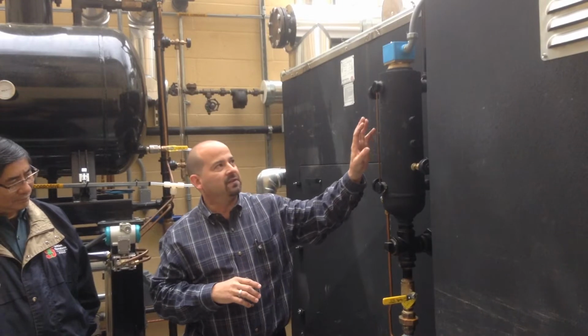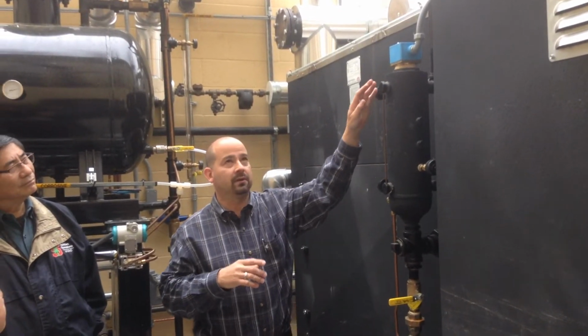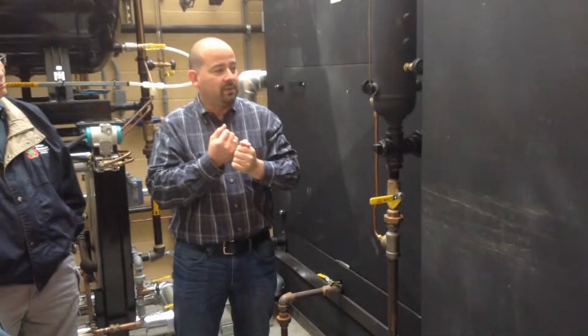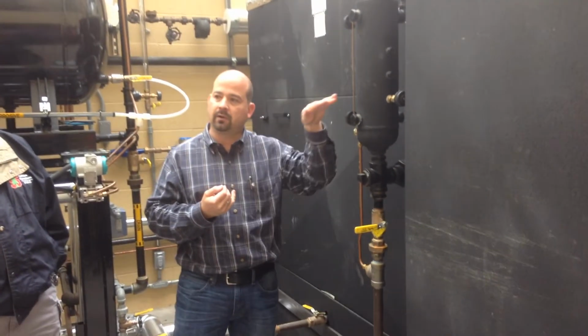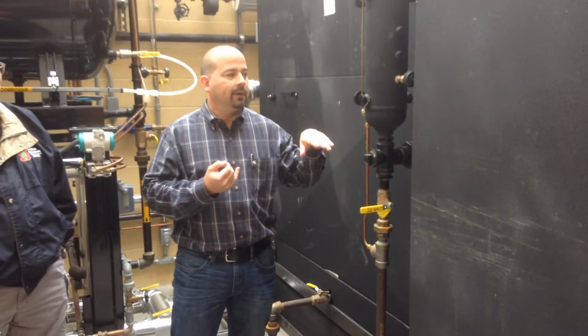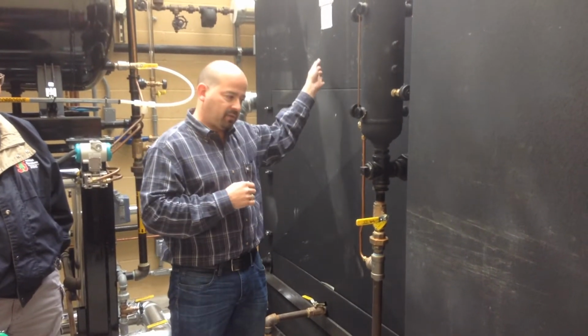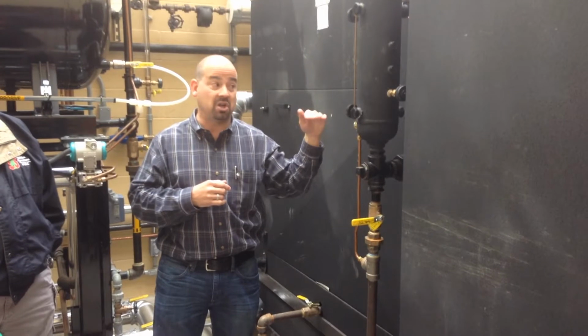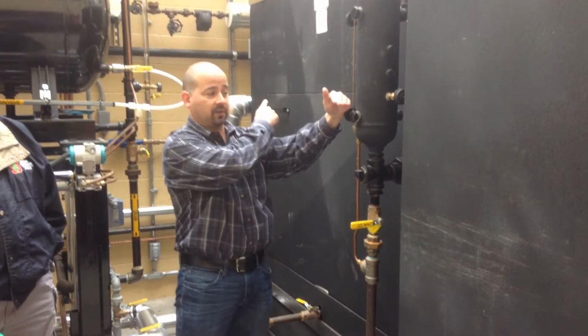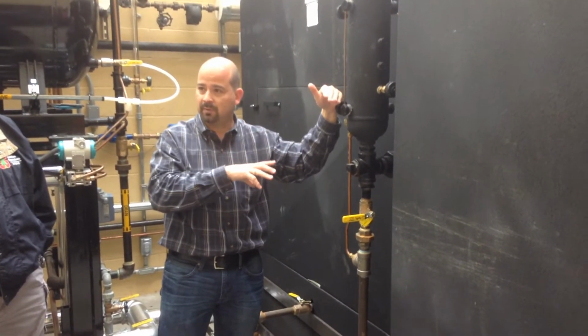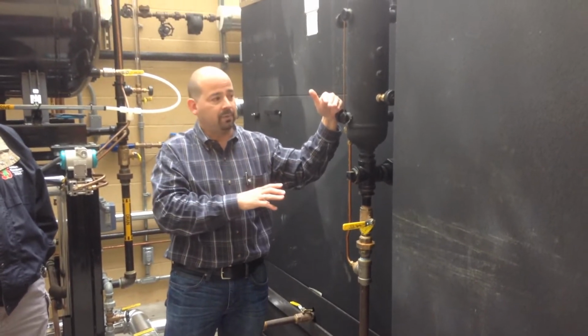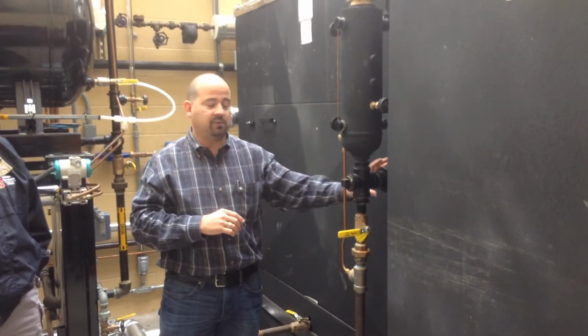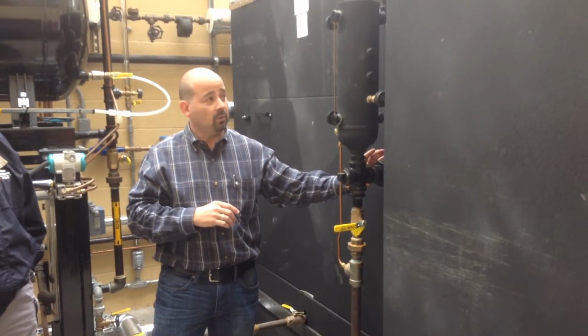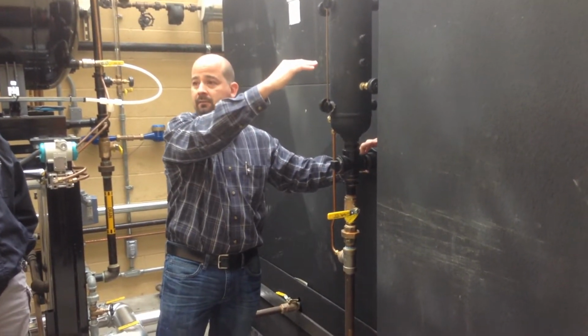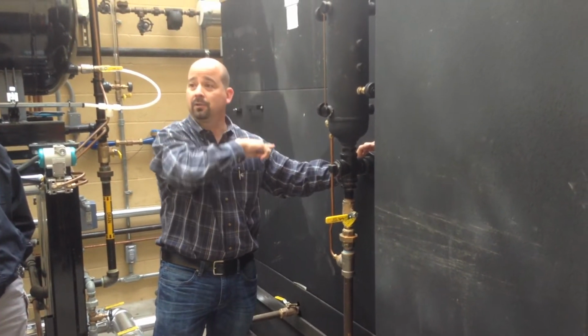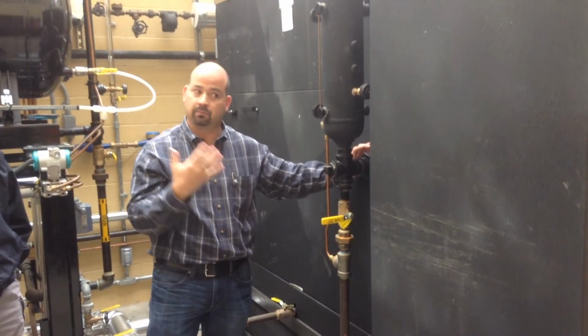And this device here has a series of probes in here, I think 4 probes. One probe is a low water probe, so if the water gets too low, it'll turn the boiler off. There's a secondary probe in a separate location. So if the water level gets too low, even beyond the low water probe on here, there's one that's a little lower, and we intentionally want that in a separate location for a good reason. Because let's say hypothetically, this pipe were to get plugged up down here. Well, this might say, okay, boiler's happy, and we're full of water, and it's firing. Well, the boiler could be melting, and just molten steel, so we obviously don't want that.